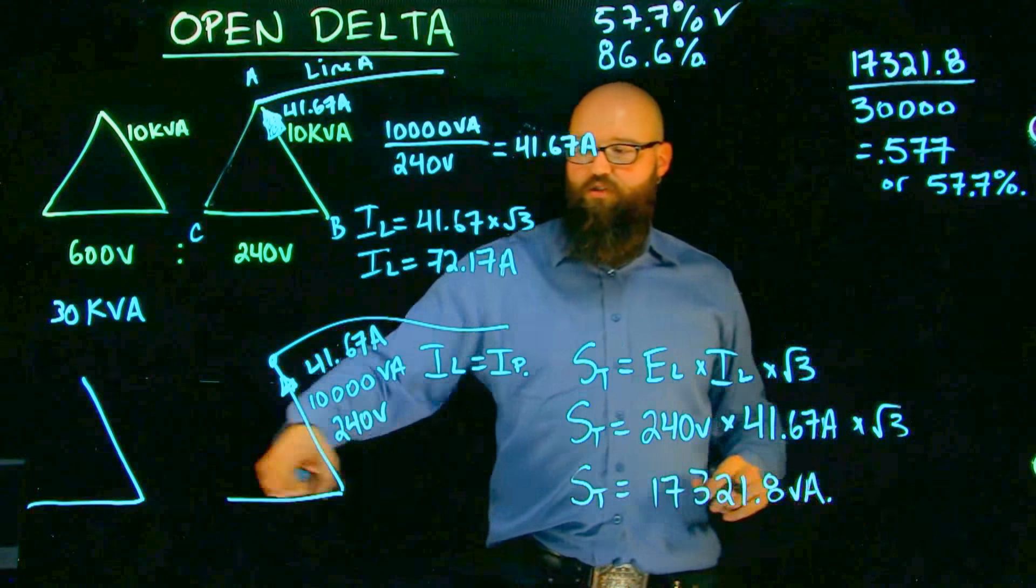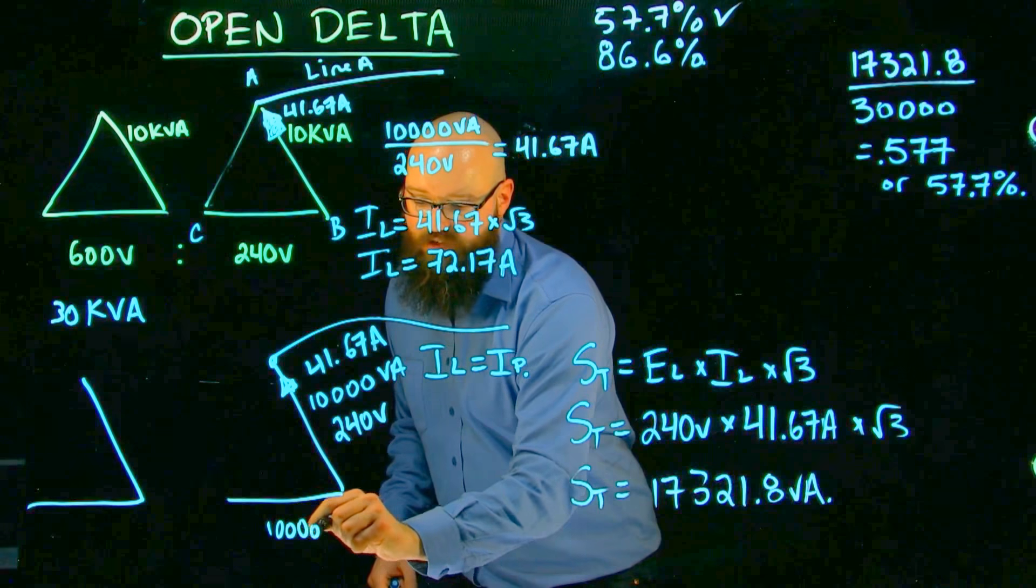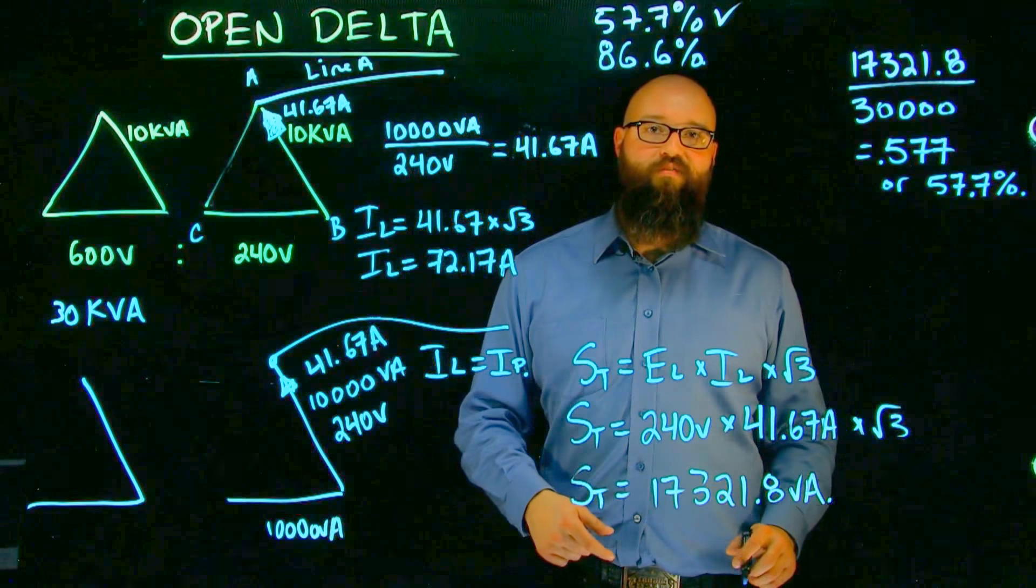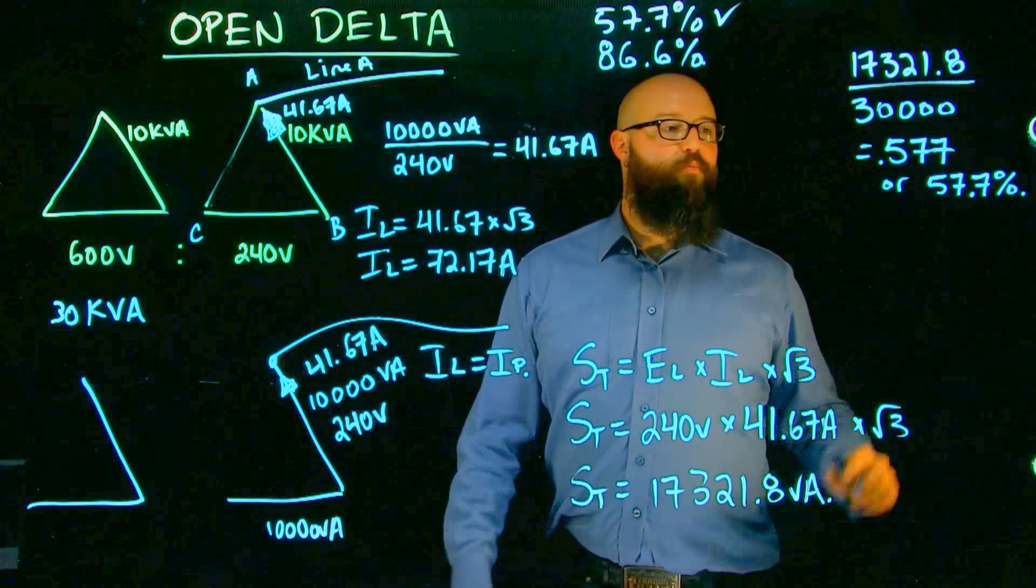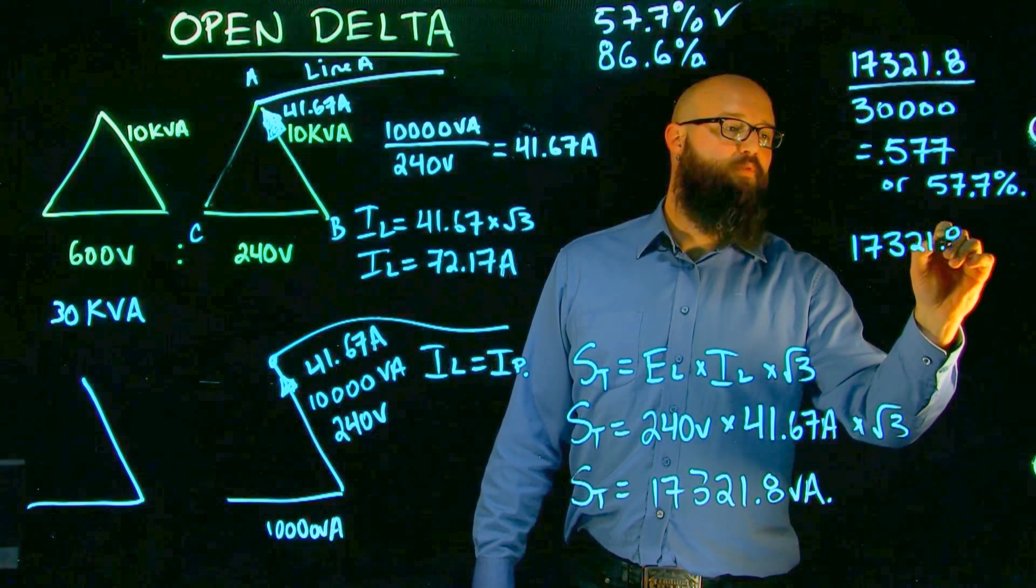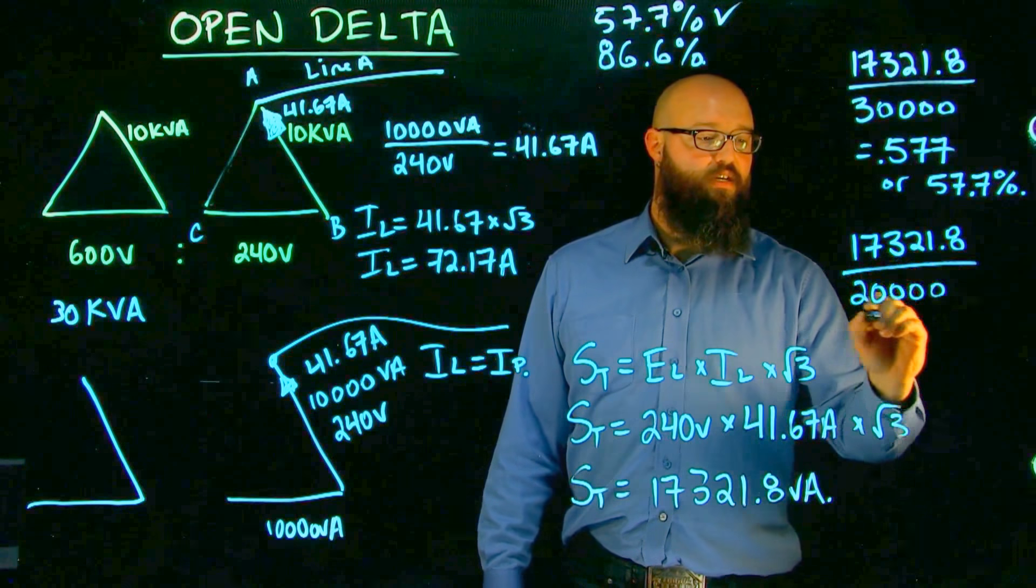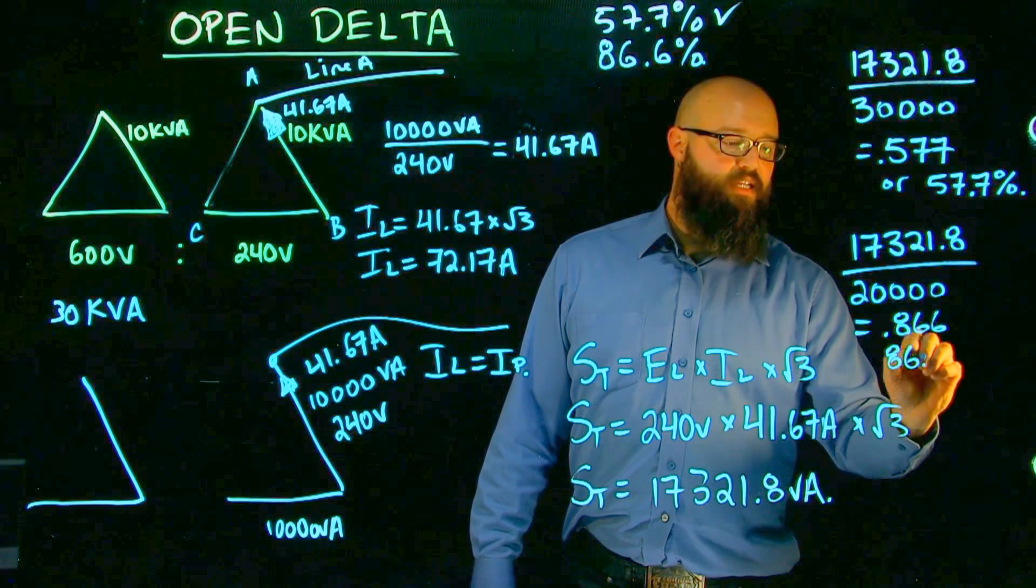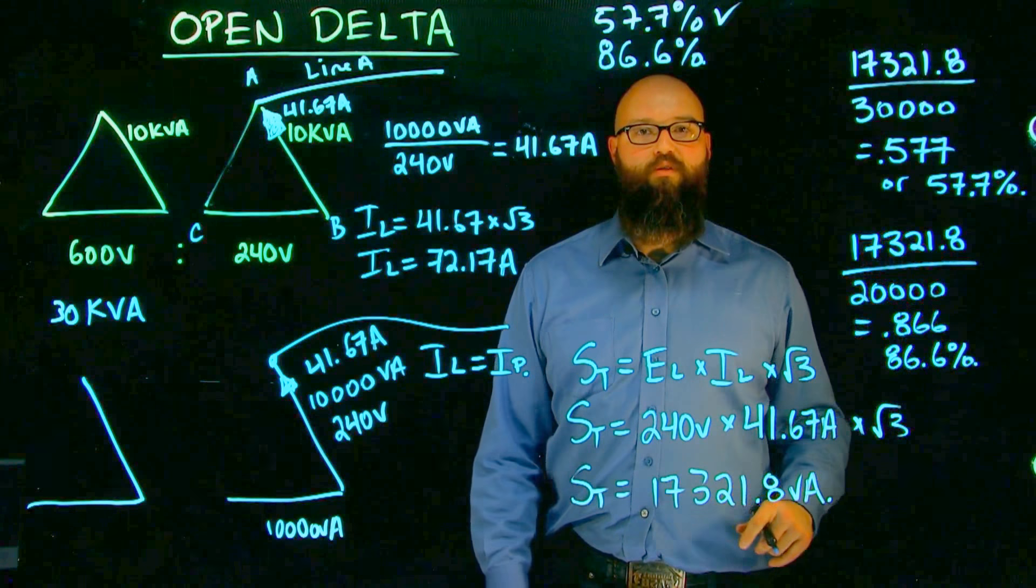If we just focus on the two coils, we can see if I have 10 kVA or 10,000 VA and another 10,000 VA, what they should be able to put out is 20,000 VA. But again, because we have this connection in open delta, what we see is this 17,321.8 compared to what they should be able to put out of 20,000 gives us 0.866 or 86.6% of reduced capacity of what those two normally would give out.